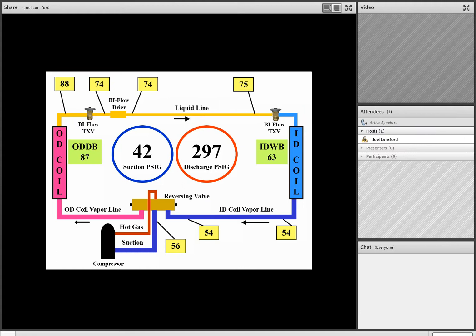The first thing that we notice on this service call is we've got an R22 service call. We have 42 pounds of suction pressure, 297 pounds of discharge pressure. You'll also notice that we've activated all the yellow temperature blocks. We have also indicated a green temperature block near the outdoor coil, and that's our outdoor air temperature. In this example, it's 87 degrees outside. We also have activated a green temperature block near the indoor coil. Now, we are in the cooling mode of operation. The outdoor coil is warm, the indoor coil is cold, and we see that we have an indoor return air temperature of 63 degree wet bulb temperature. So these two temperature blocks tell us the actual temperature of the air passing over those coils.